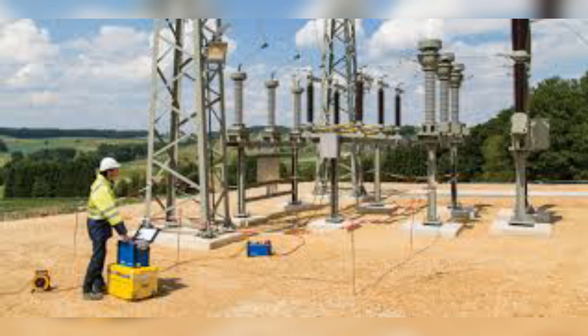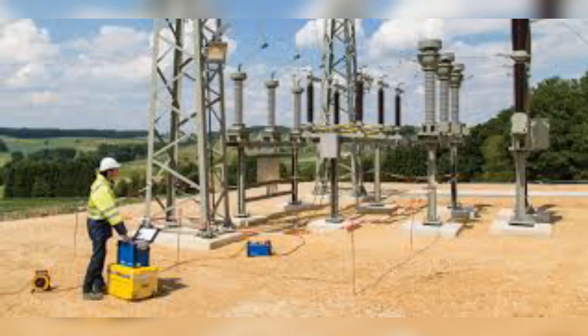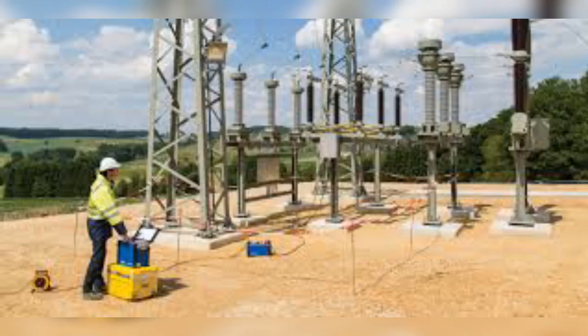Here are some tests performed on high voltage equipment, starting with the ratio test. This test verifies the ratio of the connection of a CT as well as any taps available. It can be done both in service and out of service. The out of service voltage method requires injecting voltage V1 into the secondary and measuring the primary voltage V2, which is directly related to the CT ratio.